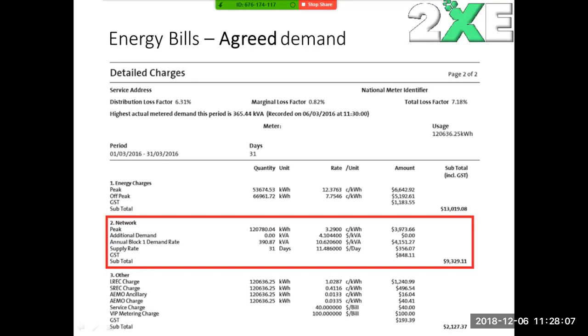What I want to point out is that the actual demand reached during that peak period was 365 kVA, meaning there's a 25 kVA difference between what they actually used and what they're being charged for. So there's potential for this winery, if they can prove they won't exceed that demand, to drop it down by 25 kVA.